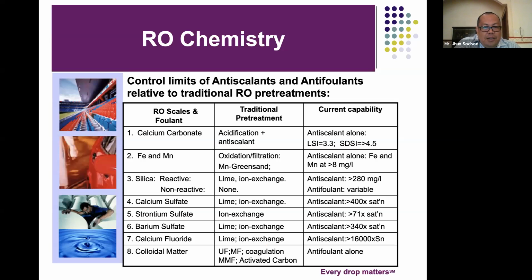The most concern is the colloidal matter, especially in wastewater recycling RO, where colloidal matter can be organic, inorganic, and sometimes even carry over of pre-treatment chemicals, especially those made of metal compounds like polyaluminum chloride and ferric chloride. Carry over of those pre-treatment chemicals is normally observed in the RO membranes. Despite having UF, microfiltration, and additional pre-treatment mechanisms, it can still be very much visible in the RO membrane. To handle the colloidal matter, we have the antifoulant, which was explained earlier by Mr. Cabrera.